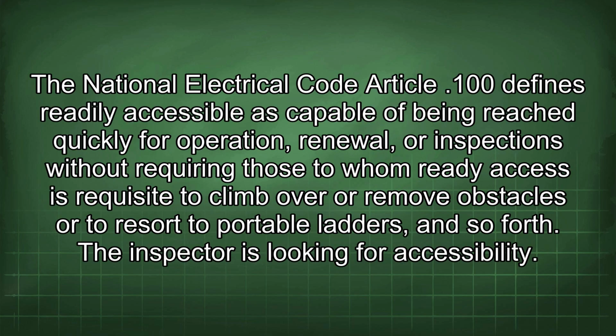The National Electrical Code Article 100 defines readily accessible as capable of being reached quickly for operation, renewal, or inspections without requiring those to whom ready access is requisite to climb over or remove obstacles or to resort to portable ladders, and so forth. The inspector is looking for accessibility.